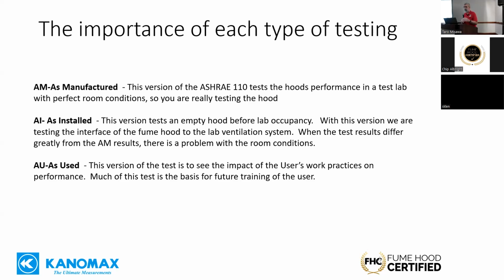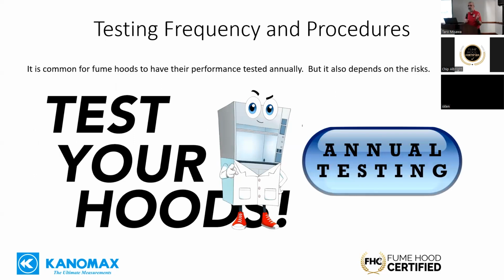Later on, after people occupy the space, we do as-used testing. That's the first time we have a loaded hood with equipment in it, and it's also going to impact things if people overload the hood or have a lot of stuff sitting on the work surface—that affects performance. With an as-used ASHRAE test, we want to compare it to the two before it. If the as-used numbers are substantially different from as-installed, something has changed in the room conditions or working practice. Between the three tests, it gives you a pretty good indication of what's happening.